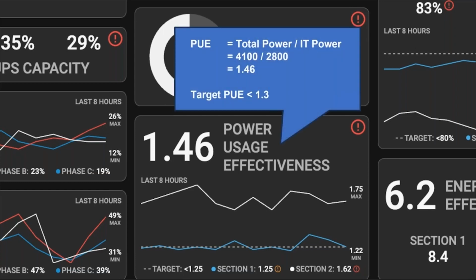And if you do the math again, like I did in the previous slide, you can see 4.1 megawatt power consumption, 2.8 megawatt to IT. So that will result in a PUE of 1.46, and it should be below 1.3.